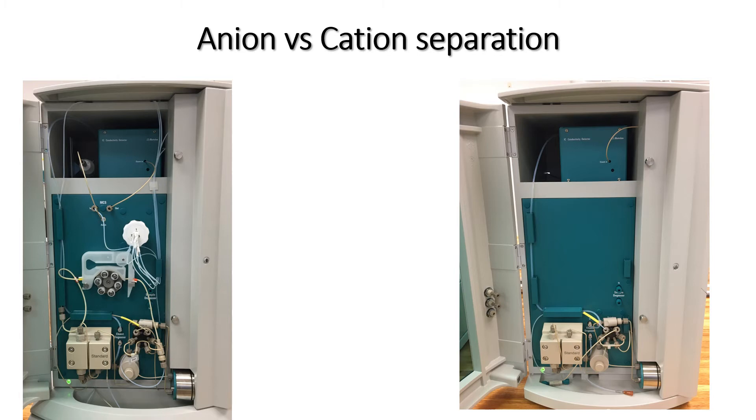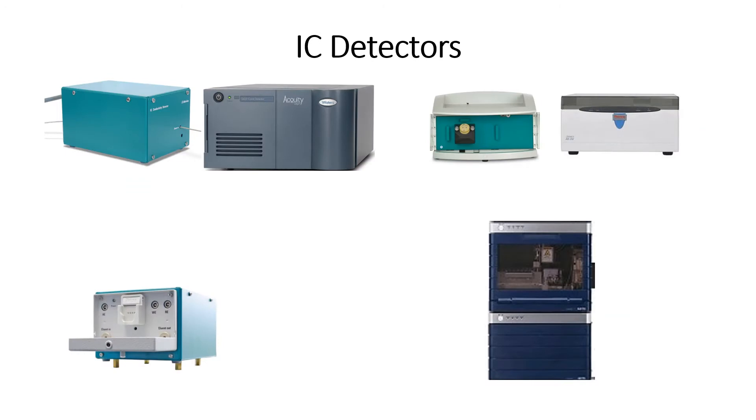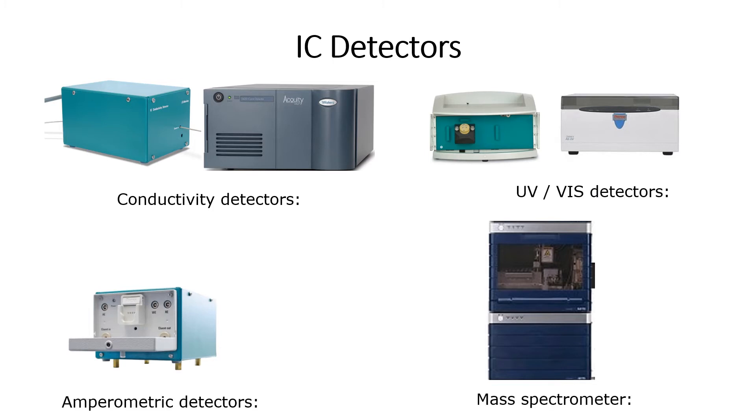Once the compounds are separated on the column, the two systems become different. The anion system has an additional suppression module. To understand the function of this module, we are first going to take a look at how the ions are detected and quantified. There are many different types of detectors and each of them work on their own principle of how the ions are detected. Examples include a conductivity detector, a UV-Vis detector, an amperometric detector and a mass spectrometry detector. The IC system which we have makes use of conductivity and UV-Vis detectors, so for this training video we are only going to focus on these two.